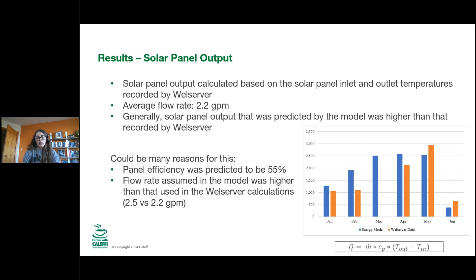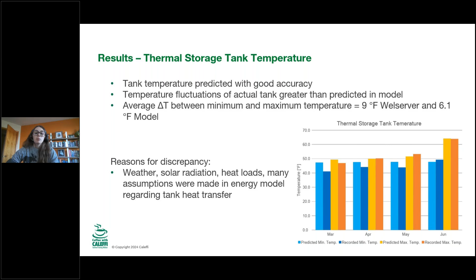The thermal storage tank is a parameter that I actually had really good success with. The tank temperature was predicted with pretty good accuracy, but the fluctuations of the actual tank were greater than what I was predicting in the model. The average temperature difference between minimum and maximum temperature was 9 degrees as measured by the Welserver, and I predicted it to be about 6.1 degrees in the model. But you can still see that the tank temperature was predicted with pretty good accuracy, which is really good because that's a very important parameter for the system. That tank temperature is really going to dictate whether or not you're using heat from the thermal storage tank or from the open loop ground source heat pump.